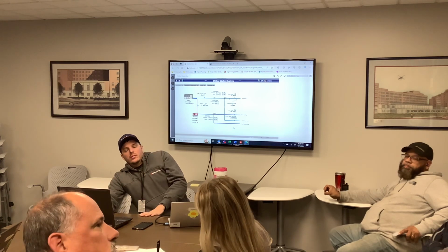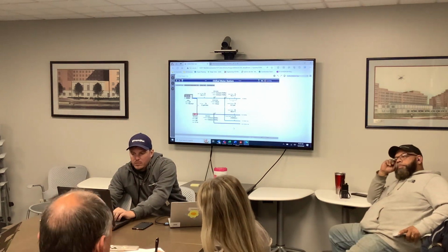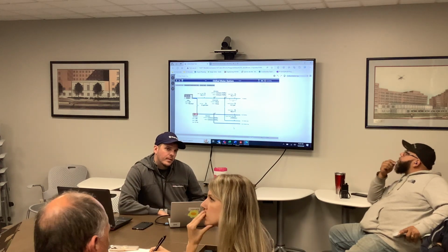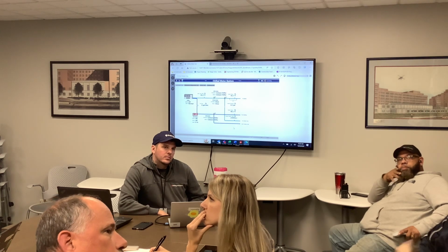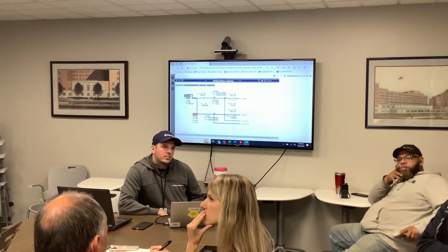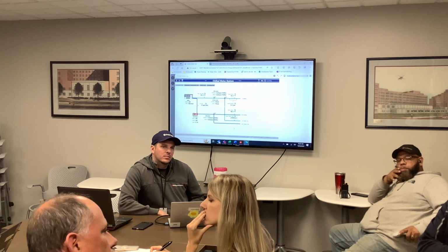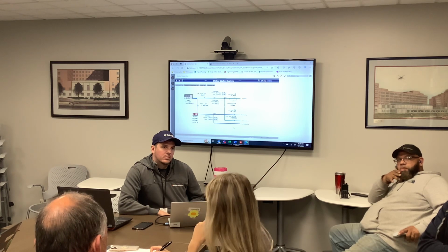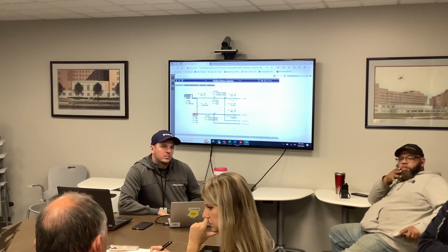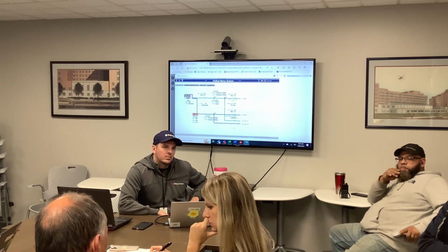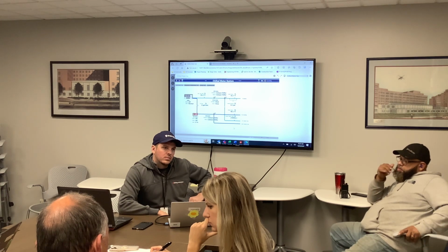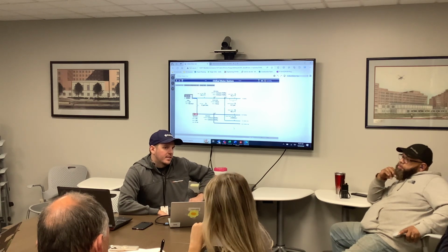And with that said too, just to piggyback on that, I like that idea. The same philosophy that I got during pressure differential. Let's say we know we're going to start freezing, especially if the water's not moving, call it 35, 36, right? So can we color coordinate these echelons? Let's say the green area would be, just throwing numbers out, 80 to 75 degrees, the amber area would be 74 to 63, and then we start getting into red. Even though it reflects the number, can you program it so it's color coded? If I can get that temperature, I can.